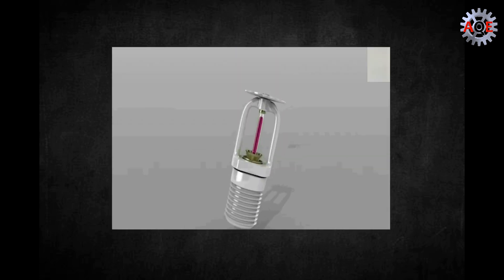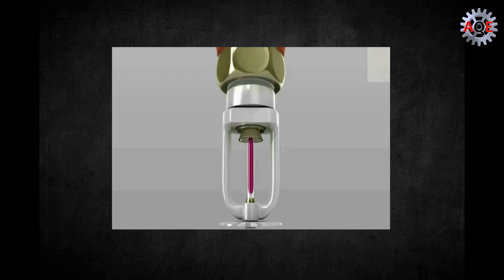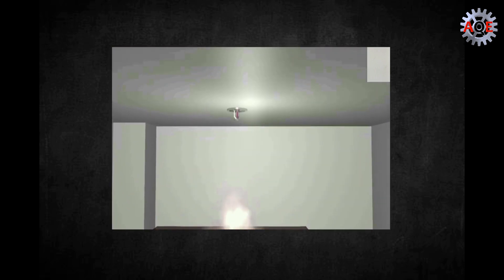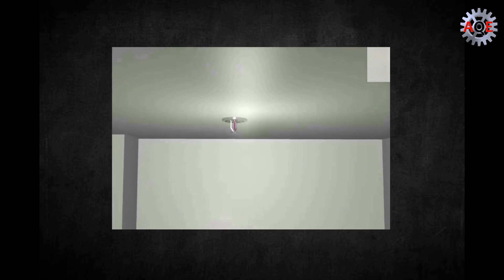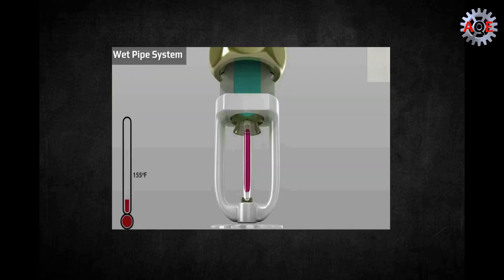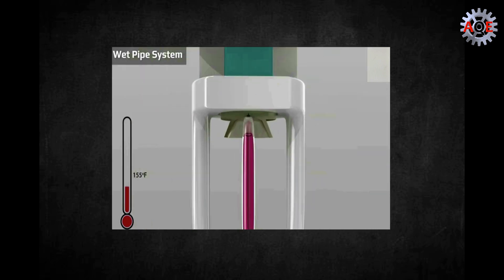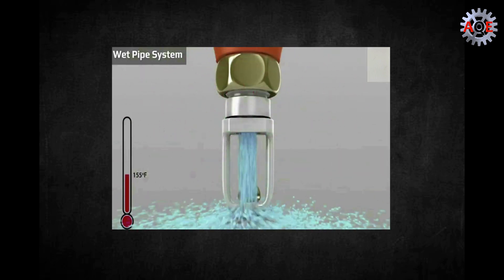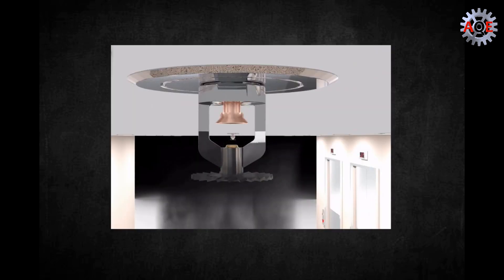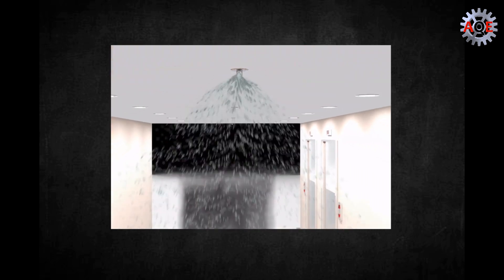Most sprinkler heads feature a glass bulb filled with a glycerin-based liquid. This liquid expands when it comes in contact with air heated to its design temperature. When the liquid expands, it shatters its glass confines and the sprinkler head activates. When heat activates a sprinkler head, a valve opens allowing pressurized water from the pipe system to flow out.